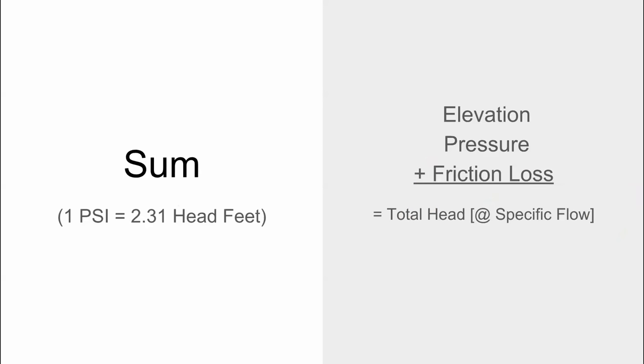In order to get your total head at a specific flow - because we're basing the friction loss on the flow through the pipe, and as the flow increases the friction factor increases - when you're doing this calculation it's only based on the specific flow that you've targeted. We simply take our elevation, add our pressure and our friction loss. The thing to remember here is elevation is already going to be in feet in most cases. Your pressure needs to be converted to feet. In order to convert pressure to feet, one psi equals 2.31 head feet. You just take whatever your desired pressure is, multiply that by 2.31, and you're going to have that number converted to feet. So you take your elevation, add your pressure in feet, add your friction loss in feet, and you're going to have the total feet of head that you need for that specific location.